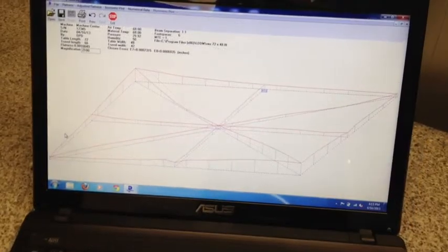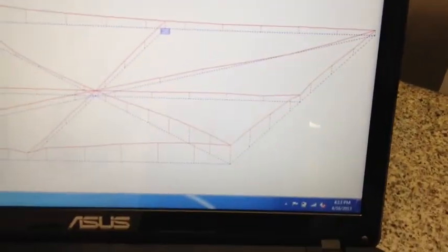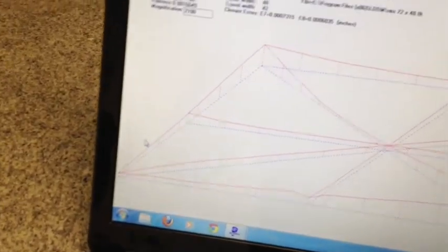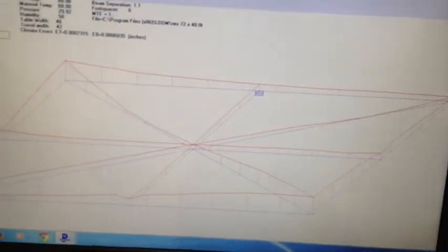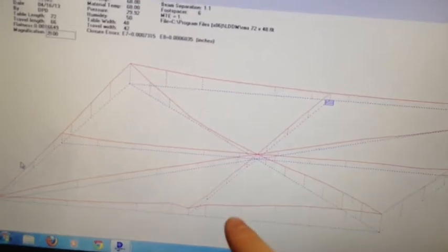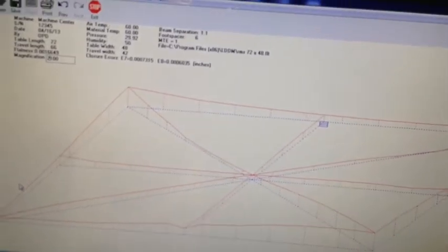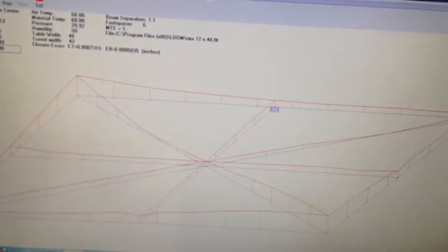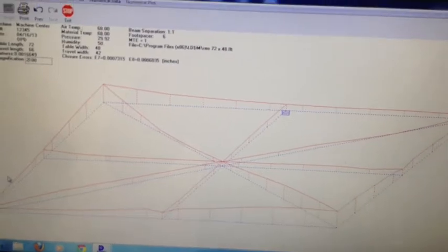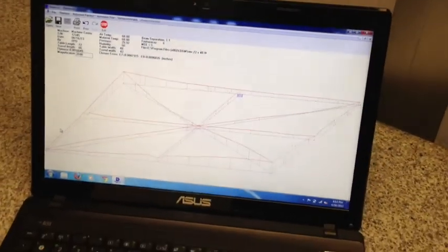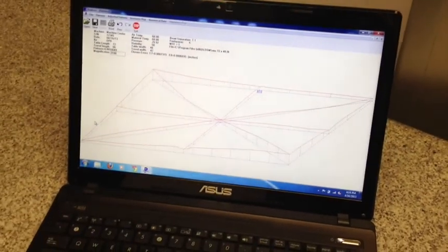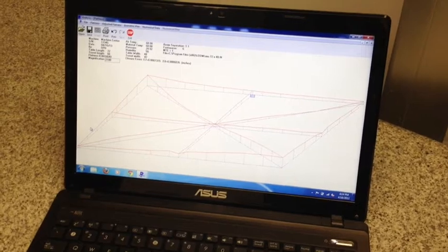As we can see, the corners are slightly higher than the center, indicating the points where the table is worn. You can see the front here. The centers all intersect. And this particular table is going to require lapping in the corners to bring it back into spec.